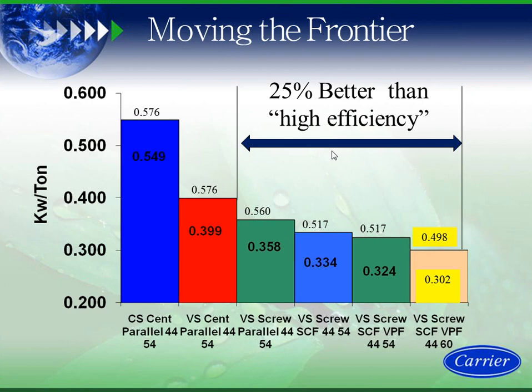Constant speed, CS, centrifugal, parallel flow, parallel chillers, 44/54. ASHRAE says I'm at 0.549, 0.576. So 0.576 full load, 0.549 part load. I now take those machines and make them variable speed centrifugals in red.